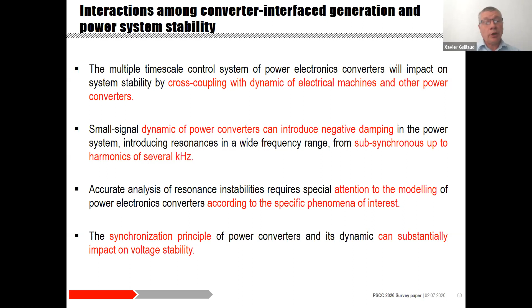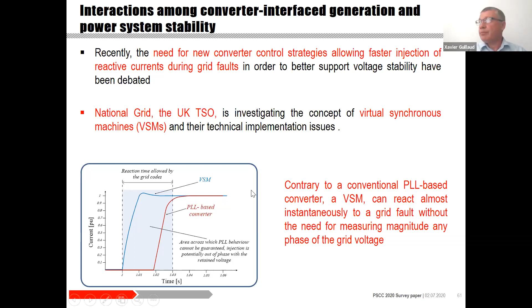Recently, the need for new converter control strategies allowing faster injection of reactive power during grid faults, in order to better support voltage stability, has been debated. National Grid, which is the UK TSO, is indeed looking at the virtual synchronous machine, which has been introduced previously. And as we have seen also, the control of a converter without PLL, a VSM, reacts almost instantaneously to grid faults without the need of frequency measurements. Recently, studies have shown the negative effect of synchronization units, often implemented by means of PLL, on the small signal stability of grid-connected converters.